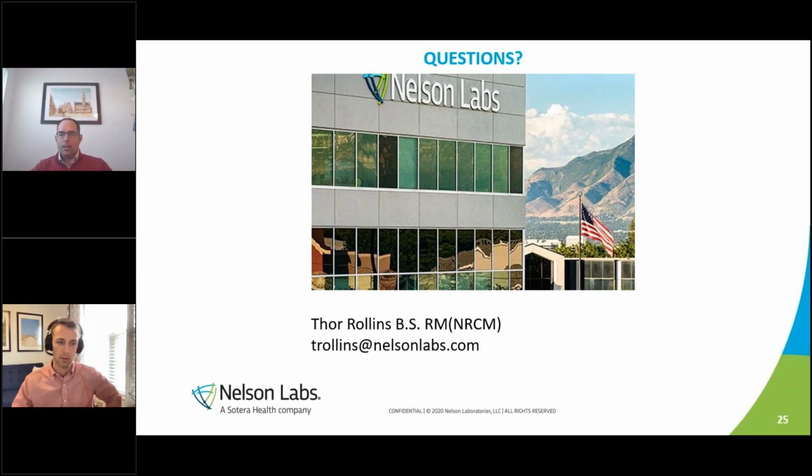Okay, thank you. Another one is, let me see here. How does this affect contract manufacturers where the end product does not have our company's name, et cetera, listed? Yeah, so there's a couple of those. When you think about biocompatibility, really the person who's responsible for the biocompatibility is the person who's selling that device. So there's a lot of people who will, for example, provide syringes or things like that to a kit, and then that's repackaged and sterilized and sold. The biocompatibility risk perspective is done on the person who's actually marketing and selling that kit in the company or in the country.